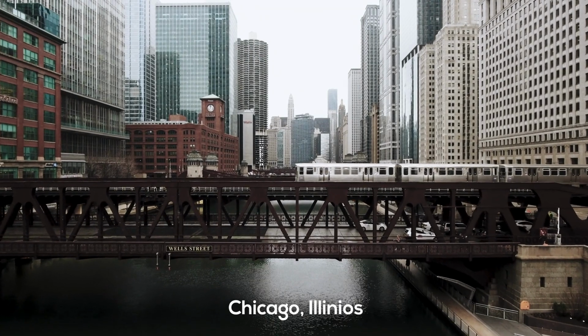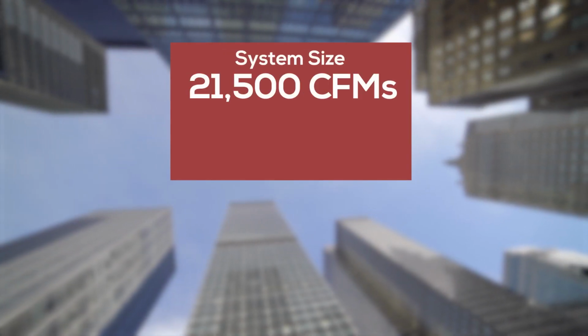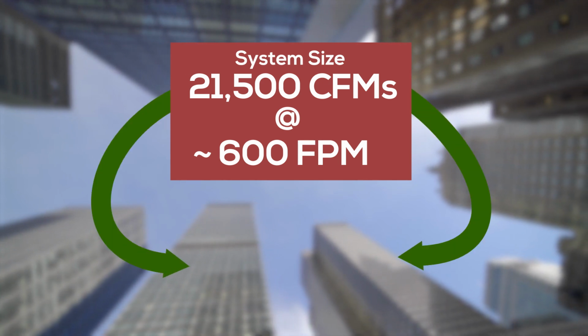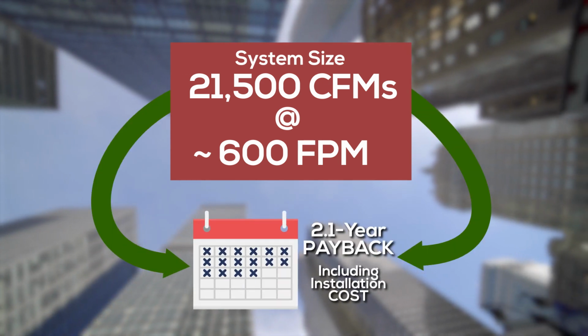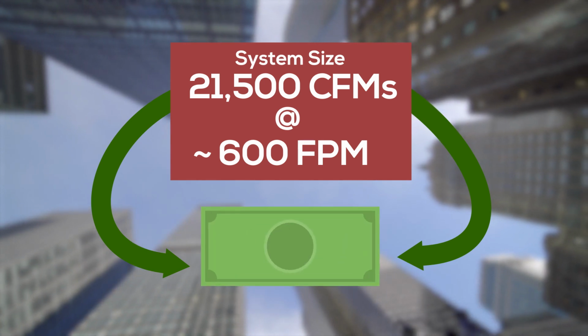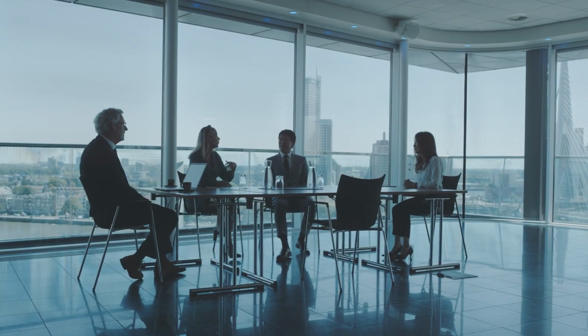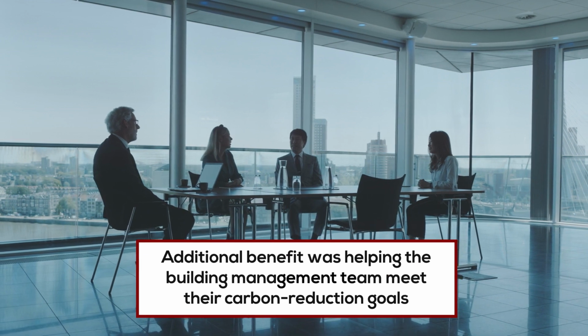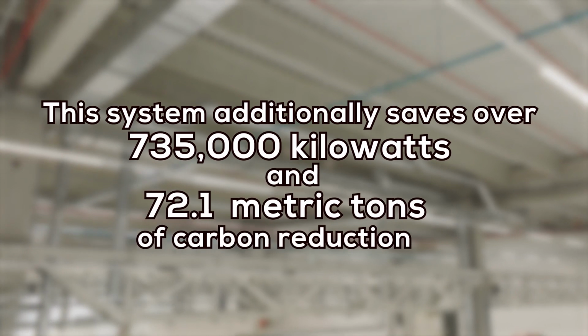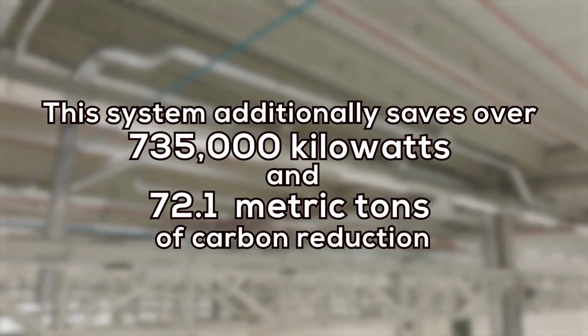The application discussed in this video was installed in Chicago. The system size is 21,500 cubic feet per minute at approximately 600 feet per minute. The resulting payback analysis yielded a 2.1-year payback period, which included the cost of installation. The system will produce an annual utility savings of $101,484. An additional benefit was helping the building management team meet their carbon reduction goals. This system annually saves over 735,000 kilowatts and 72.1 metric tons of carbon reduction.